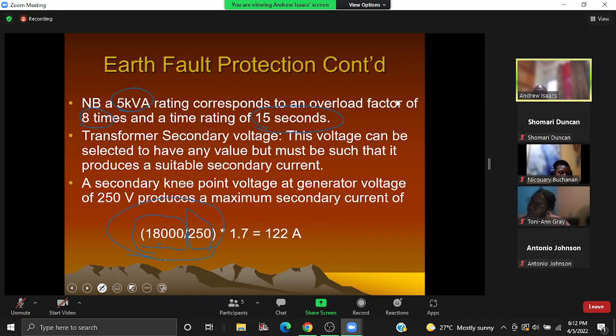The loading resistor now, and this is the beautiful point. Know that I have selected, because remember, this 250 isn't a value that I have been given. All we know is that it must be between 100 and 500. And I am selecting a value of 250 on the secondary so that my secondary current will be large enough. Go back to where we started. Where we started is that we want to limit the current going through the earthing point. But we said in limiting that current, we're going to impact our relaying. So we have to find a way to balance it. So from 1.7, I now have 122 amperes that I'm playing with on the secondary.